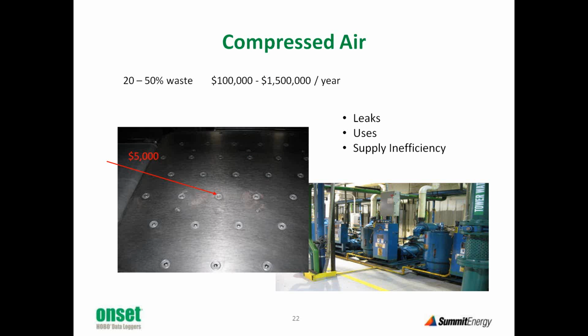Just one more example around compressed air. This is a printing operation where large stacks of board, of heavy paper, move along an air table here. And these are little ball bearings that close off the airstream, and when the stack of paper rolls by, the balls are depressed slightly and open up a passage for air to float the stack of paper. So I noticed in one of my visits that one of the balls was missing. So what? The operators get used to hearing that hissing sound. It just becomes the sound of doing business, not realizing that $5,000 worth of air passes through that one hole every year.